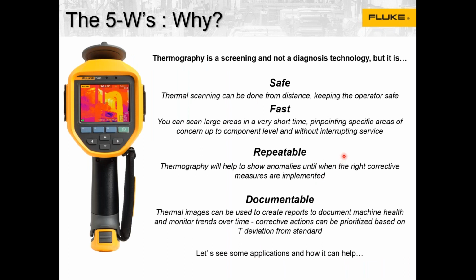So why use it? We already spoke about different reasons, mainly safety first: thermal scanning can be done from a distance, keeping the operator safe. It's fast, you can scan a large area in a short time, pinpointing specific areas of concern down to the component level, without interrupting service. It's also repeatable, helping show anomalies until the right corrective measures are implemented.